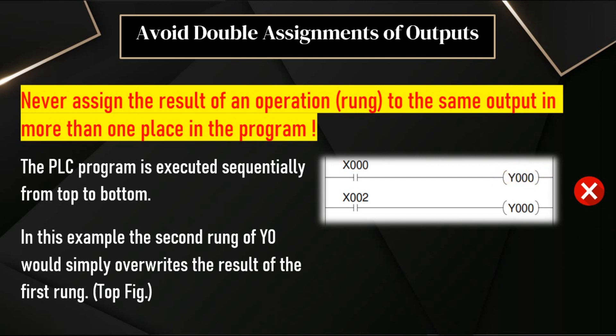The both inputs X0 and X2 may or may not have same status. Accordingly, the Y0 will be updated. This leads to the problems because the Y0 will not be updated correctly, either it updates according to X0 or X2. In some PLCs, the last instruction has some priority. In those cases, the last instruction will be executed instead of the first instruction. So we have to avoid double assignments of outputs.